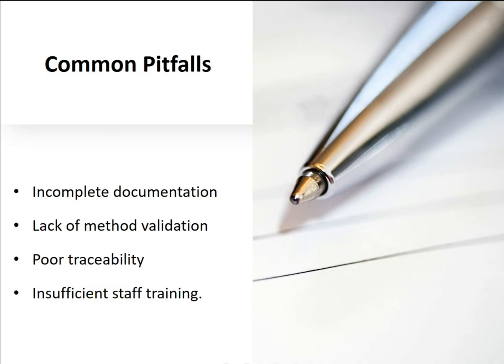Poor traceability. At the heart of all biochemistry, it's an indirect kind of measurement. You compare your values, based on absorbances, with known absorbances of standards or calibrators. These standards and calibrators need to be traceable to something acceptable and really accurate. To give an example, when you say a dimension of 1 foot, the scale ruler has to be calibrated to the international metric system. Similarly, all our standards and calibrators have a reference calibrator and standard to which they are traceable. If you don't have that traceability, you are not sure how good your calibrator is and whether it is actually working properly or not. Of course, there are some safeguards in the instrument. If it is too far off the mark, it will not let your assay go ahead.